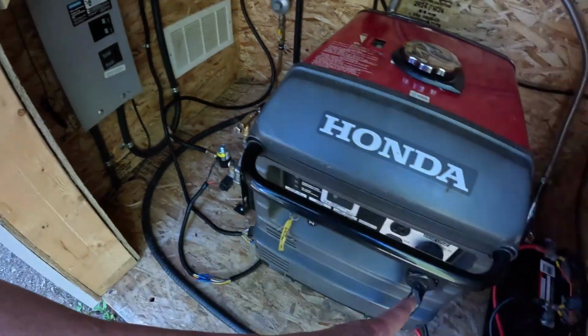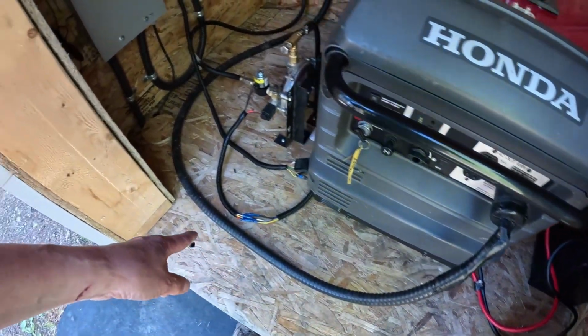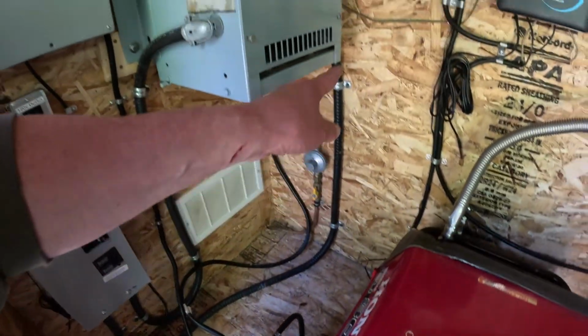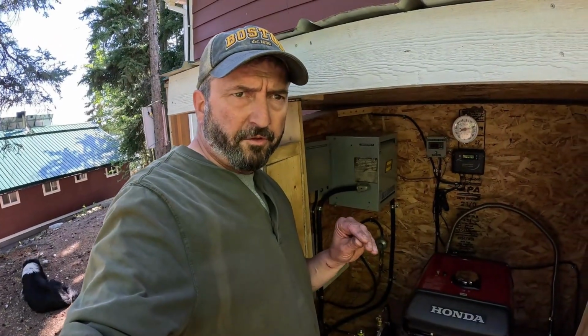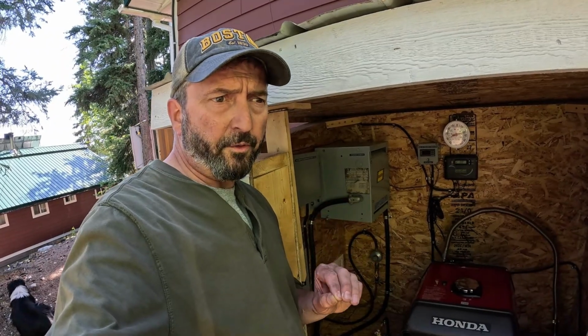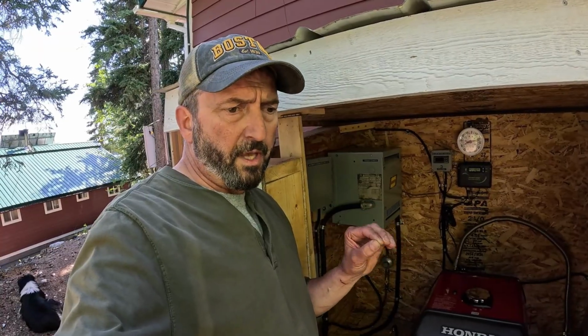Now, the power is going to come from the generator out into here, into this transformer. So why do we need a transformer? Because the Schneider XW Pro and the XWs are inverter chargers, and they require a 240 volt input for their charging system. You can jumper it to make a single phase, but if you're going to keep it in split phase at 240, you've got to get 240 volt to it in order for the charger system to operate and utilize grid power, which I'm using a generator for to charge your battery system.